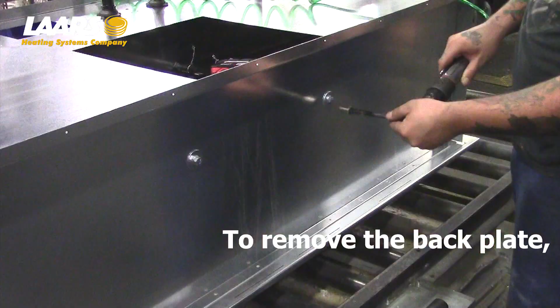So now with all the screws removed, they're actually going to take the back plate off. Now also, on larger sizes, you're going to have two bolts that holds the cross member from the heat exchanger so the heat exchanger doesn't bow. You're going to take those two bolts off and then you can take the back wall out once everything's undone.